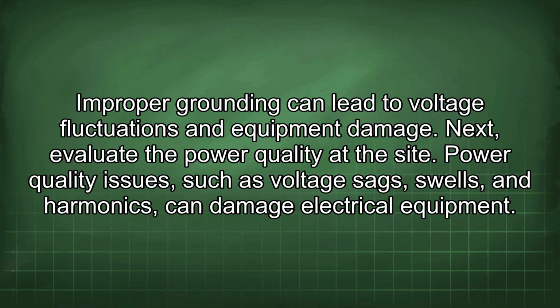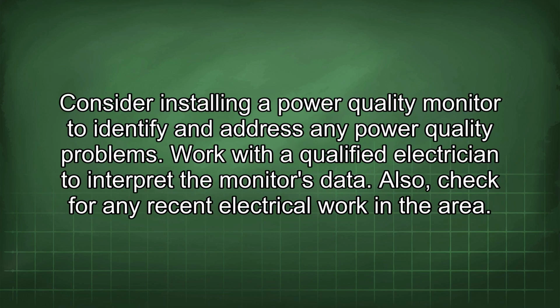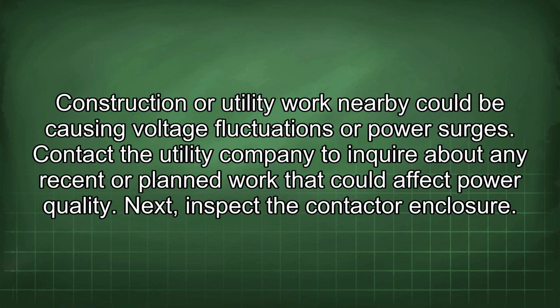Next, evaluate the power quality at the site. Power quality issues such as voltage sags, swells, and harmonics can damage electrical equipment. Consider installing a power quality monitor to identify and address any power quality problems. Work with a qualified electrician to interpret the monitor's data. Also, check for any recent electrical work in the area. Construction or utility work nearby could be causing voltage fluctuations or power surges. Contact the utility company to inquire about any recent or planned work that could affect power quality.